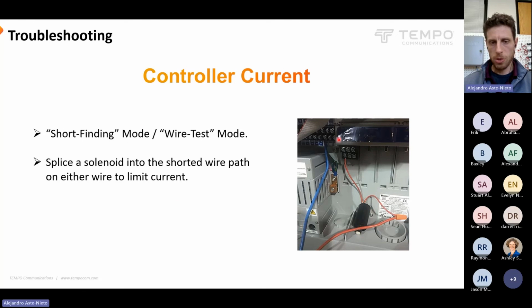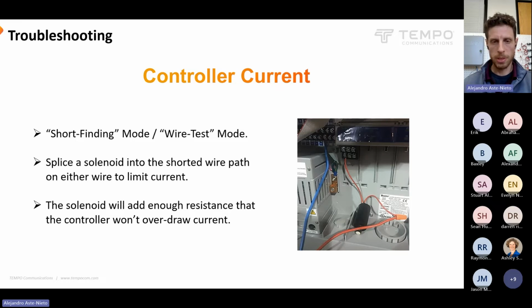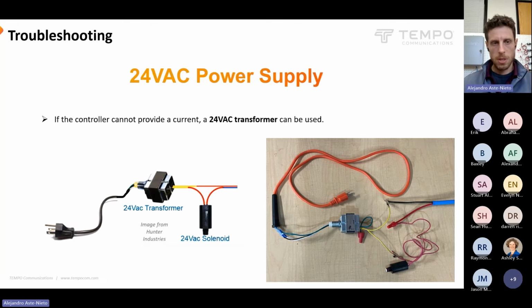So yeah, adding a solenoid to just one of the wires might be good enough to do some short troubleshooting using the controller as our power source, unless it's permanently damaged, and then you've got a bigger problem. The solenoid is made to operate off of 24 volts AC, so it's going to take that AC signal and give you a safe amount of voltage on for the controller. But if the controller can't help you there as far as being a source of current, we can make our own.